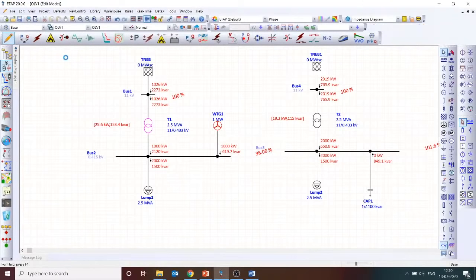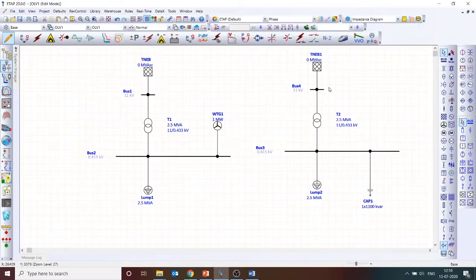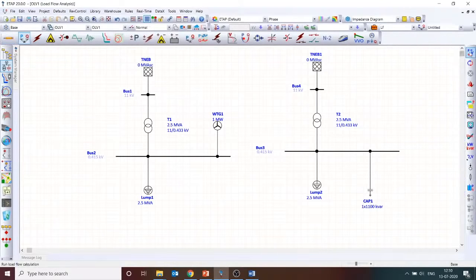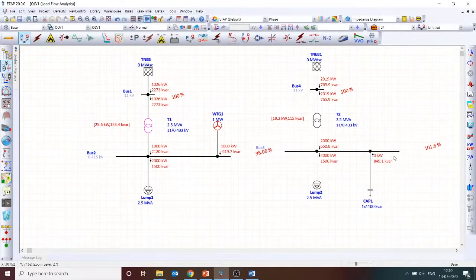So now I am adding the same capacitor. By adding the 1100 kVAR capacitor bank, I have done two important things which I have to stress. Compared to previously, the capacitor bank has enhanced the voltage profile. That's one. Second, it has reduced the losses. Previously the loss was about 28 kilowatt, and now it has been reduced. It has also reduced the reactive power loss. Previously the reactive power loss was about 170 kVAR, and now it has been reduced to 115 kVAR. That's the most important thing you need to talk about, right? So the capacitor bank has boosted the voltage, reduced the reactive power loss and reduced the real power loss. Those are all the advantages. If you want to know more about the power factor, we have power factor part 1 and part 2 on our YouTube channel, which you can watch for better understanding.